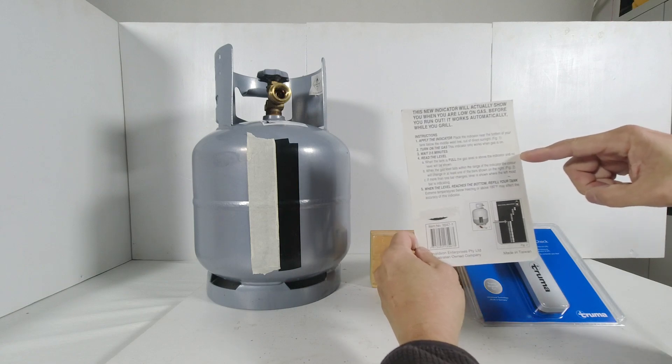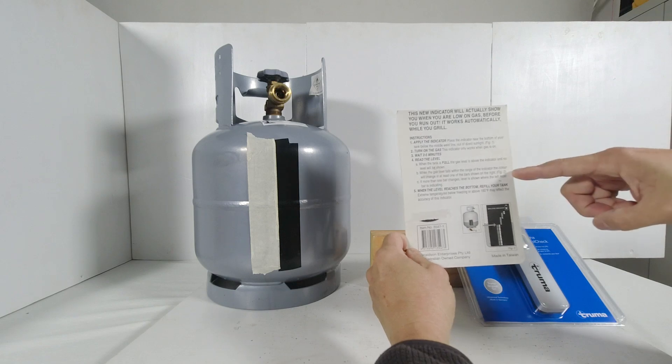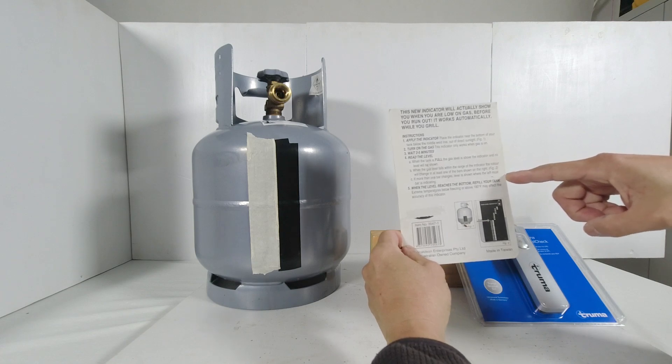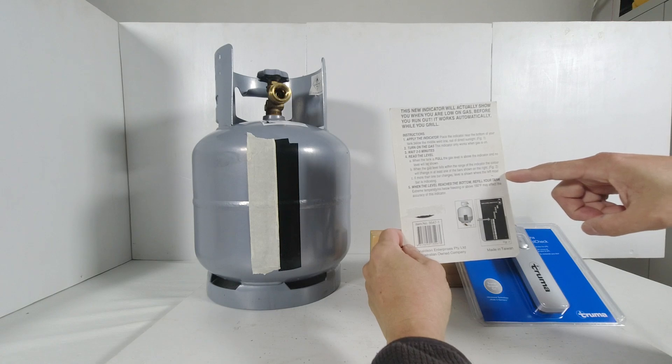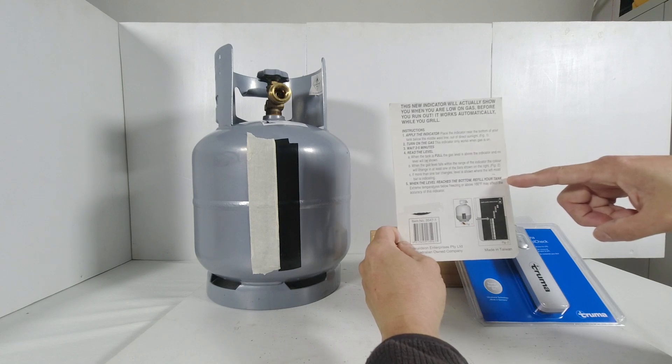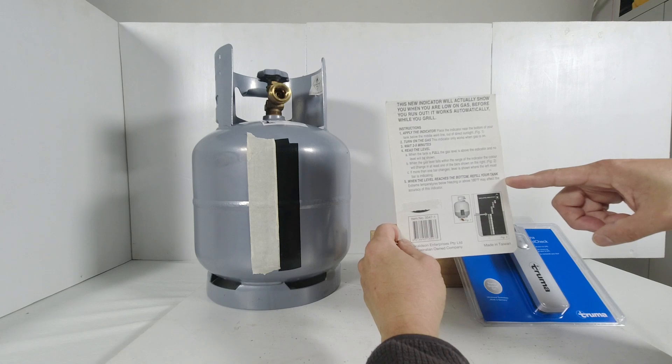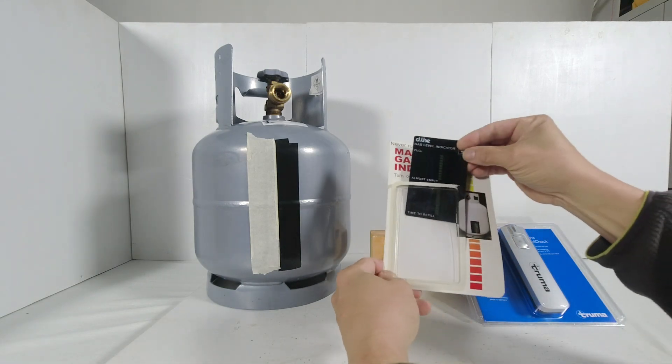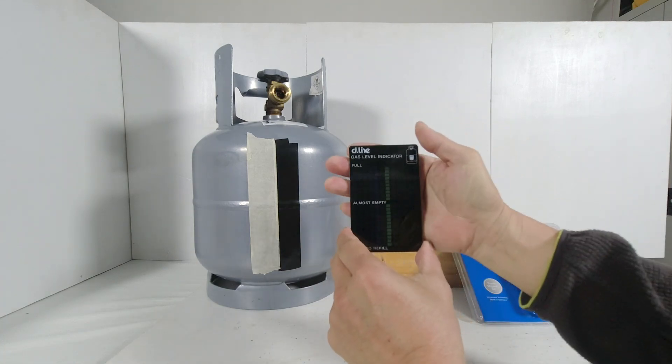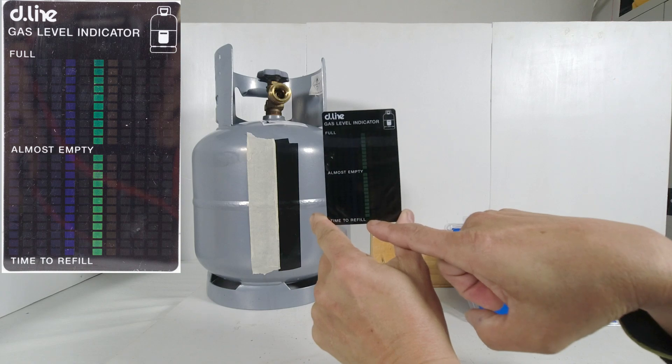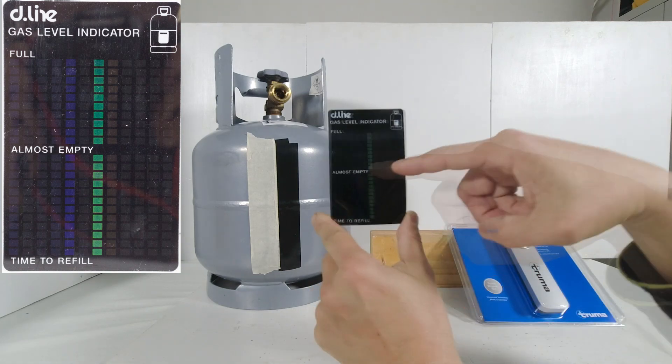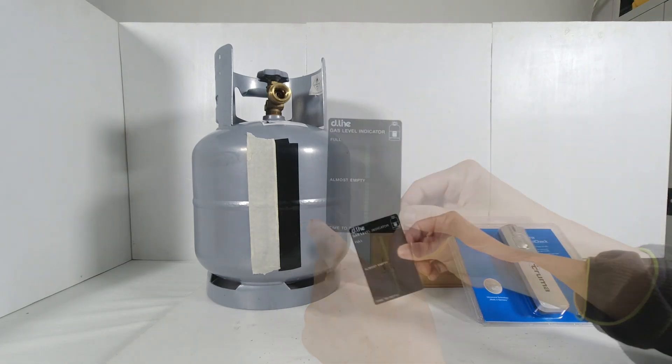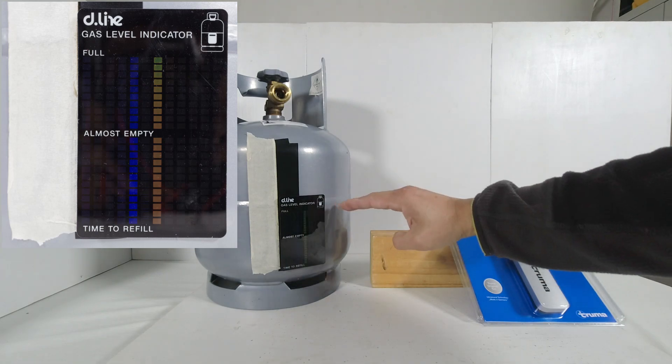When the tank is full, the gas level is above the indicator and no level will be shown. When the gas level falls within the range of the indicator, the color will change in at least one of the bars. If more than one bar changes, the level is shown where the leftmost bar is indicating. When the level reaches the bottom, refill the tank. Extreme temperatures below freezing or above 100 degrees Fahrenheit may affect the accuracy of this indicator. So place the magnetic indicator strip here below the weld line.